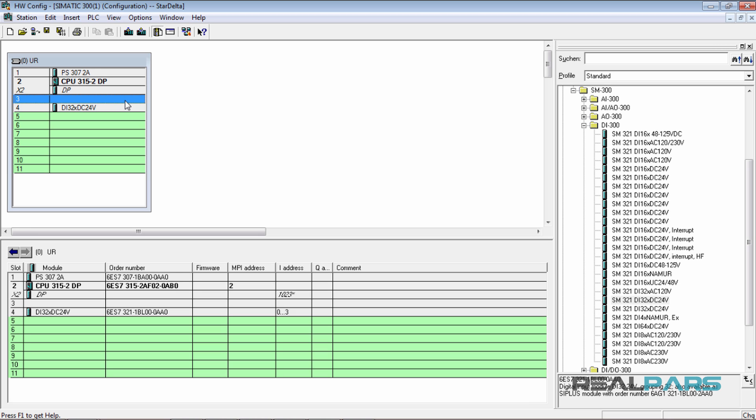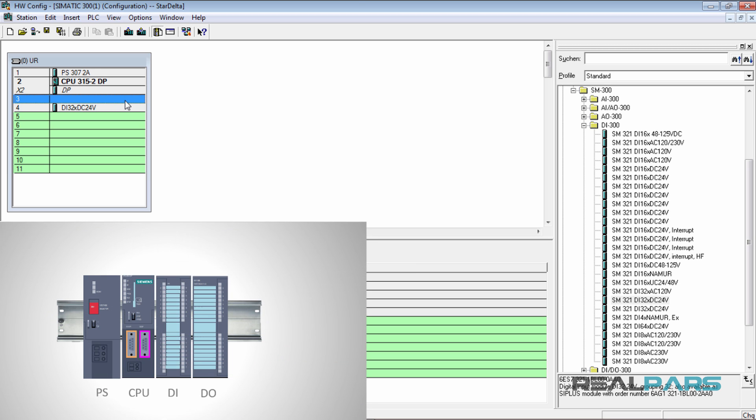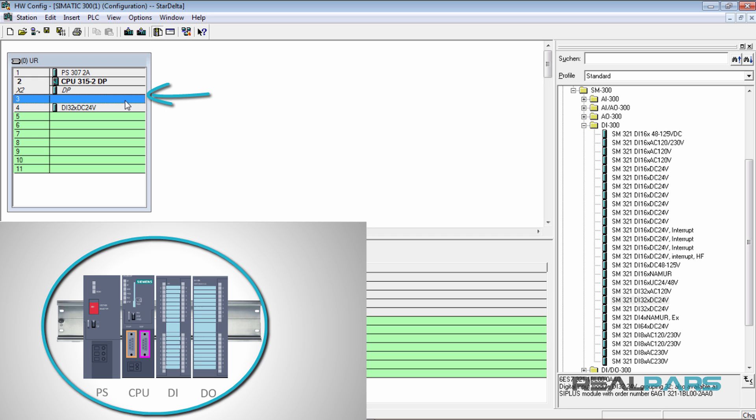The answer is no. Why? Because if you do that, the CPU won't be able to communicate data with the rest of the PLC modules. So when you don't have an interface module in your project, you leave slot 3 empty in the software, but in the actual environment, you place the PLC modules right next to each other and without any empty space.